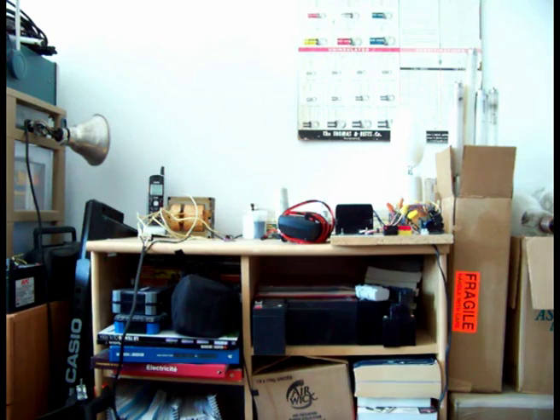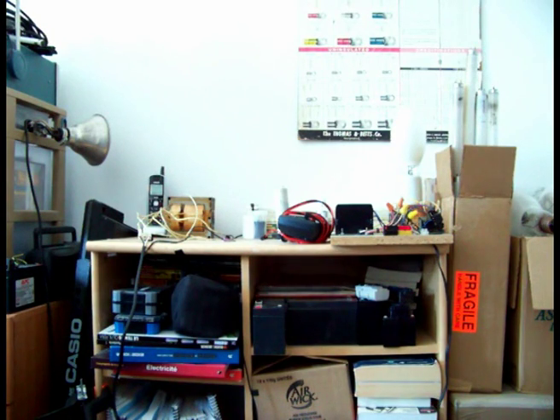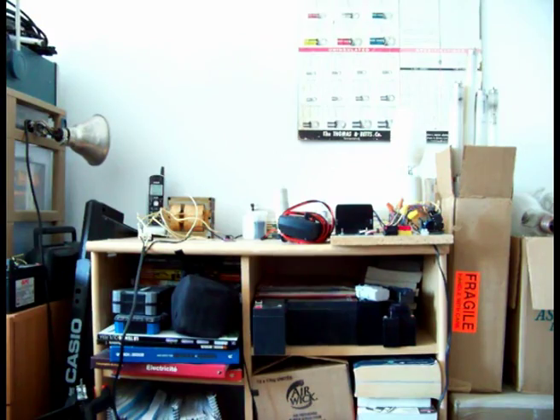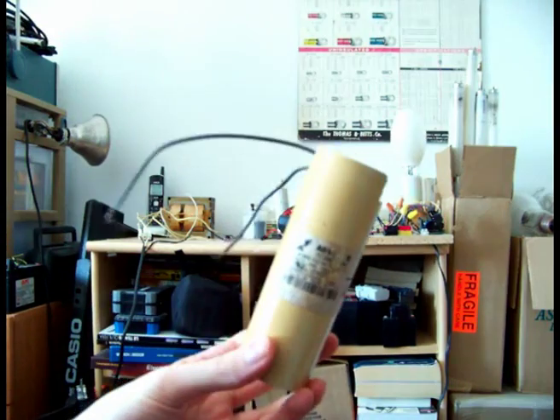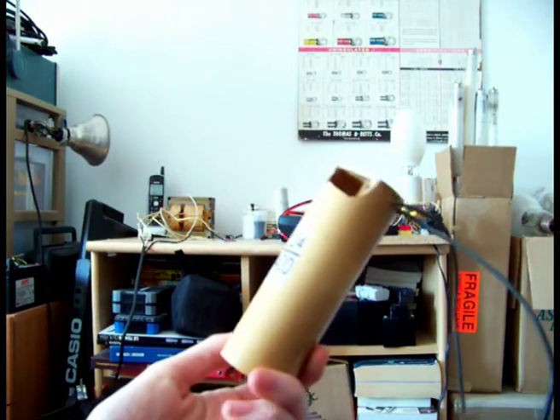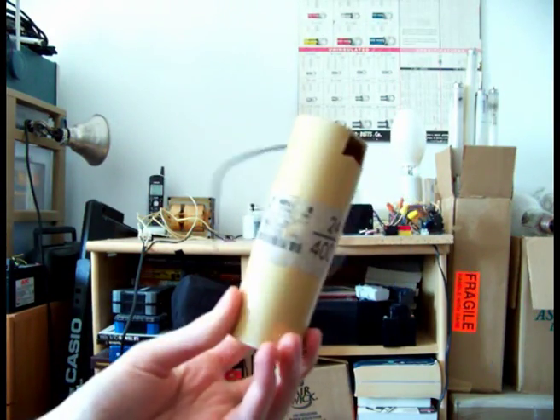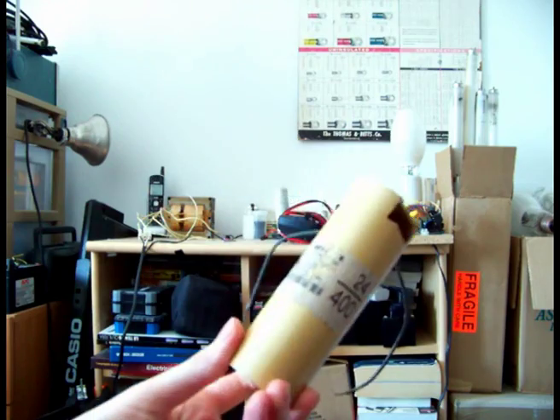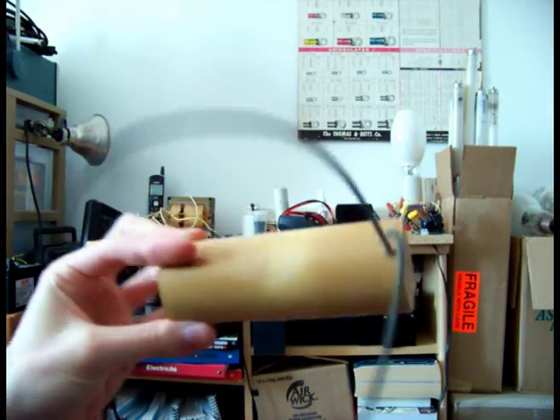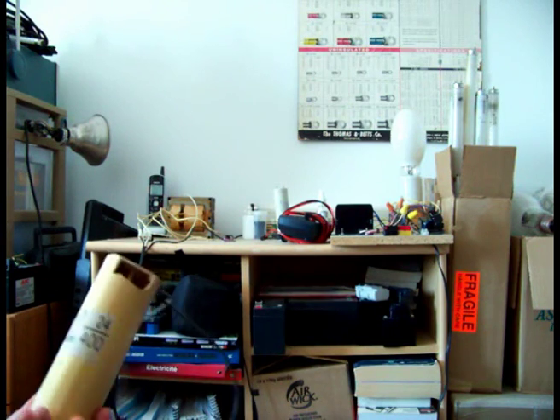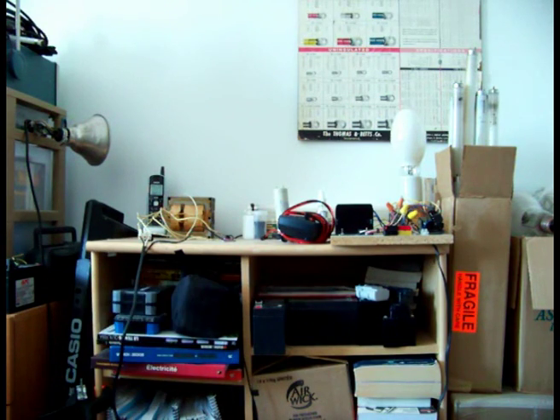I tested it with the original 24 micro farad capacitor, one I had. But by looking at it, you can see that it's not really reliable. It does test good, but it's so dried up that I would not use this on a regular basis.